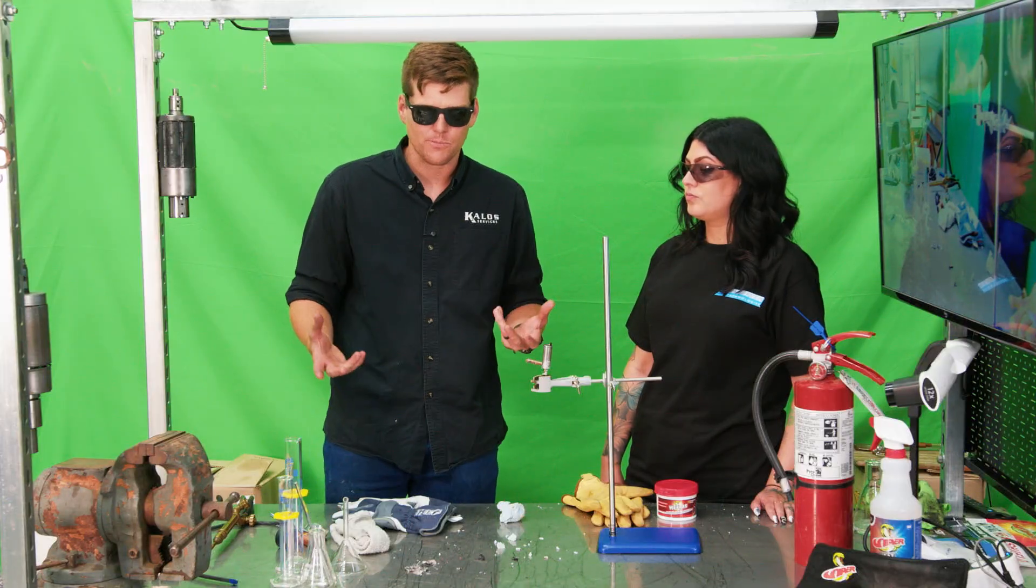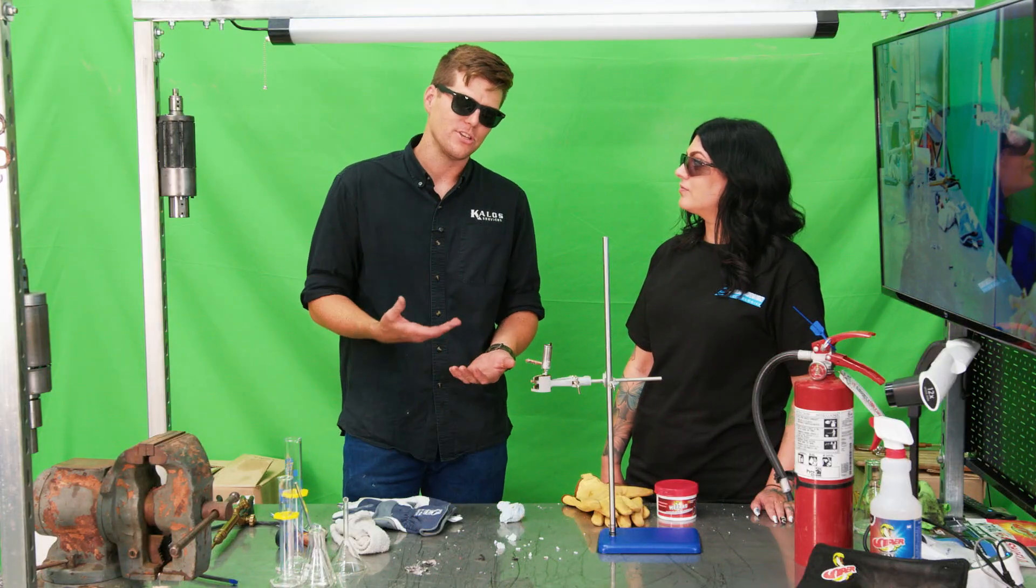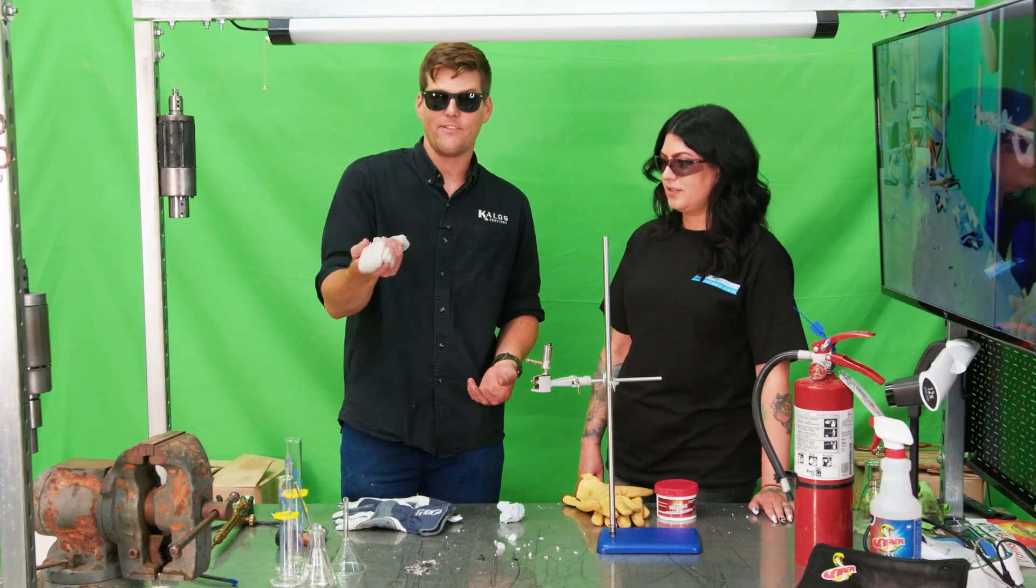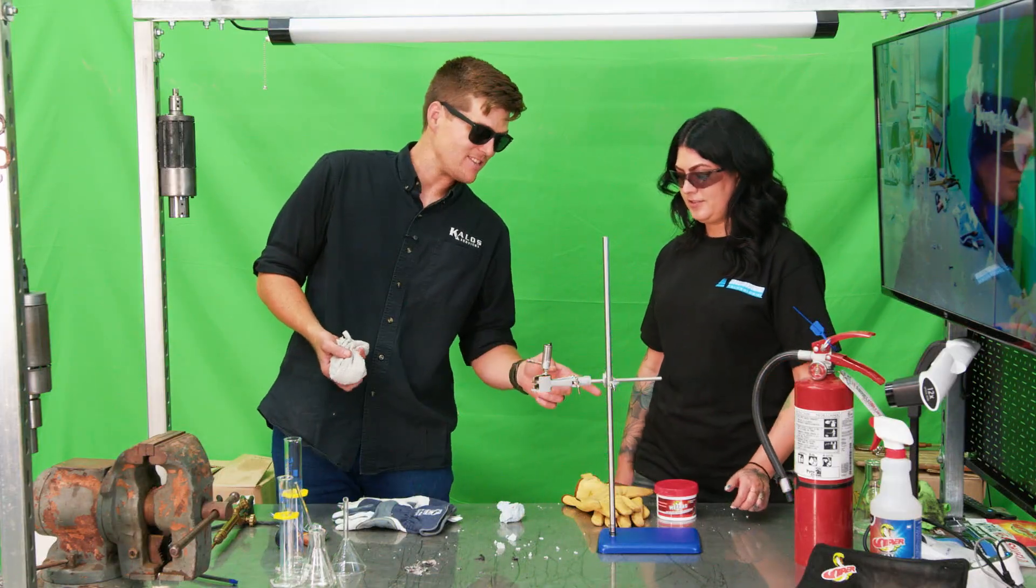or evacuate it correctly, then moisture in the system is going to turn into an acid. And that acid is going to cause all sorts of problems with my internal components, my compressors, everything. So again, although this looks like a safe option, I would stick with this.